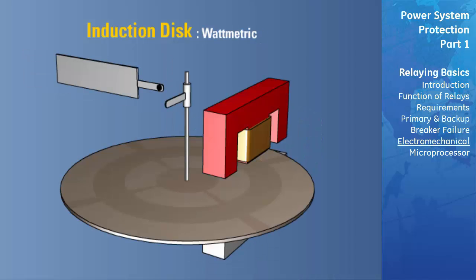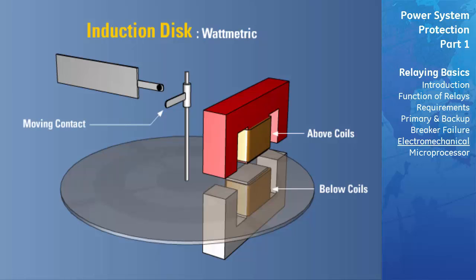Watt metric: This style uses one set of coils above the disc and another set of coils below the disc. In either case, the moving contact is carried on the rotating shaft of the disc element. The induction disc style of relay is always used as a time delay element because of the inertia of the moving disc. The time delay feature is added by means of a permanent magnet. The disc rotating between the poles of this magnet causes an induction drag.